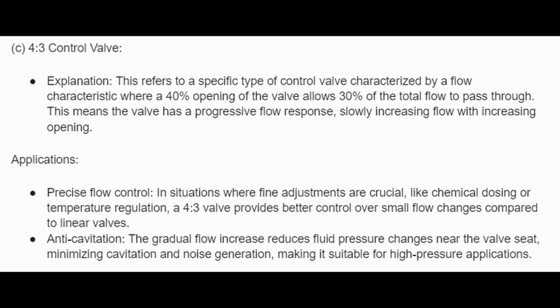Applications. Precise flow control. In situations where fine adjustments are crucial, like chemical dosing or temperature regulation, a 4 to 3 valve provides better control over small flow changes compared to linear valves. Anti-cavitation. The gradual flow increase reduces fluid pressure changes near the valve seat, minimizing cavitation and noise generation, making it suitable for high-pressure applications.